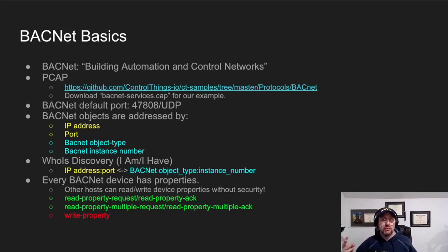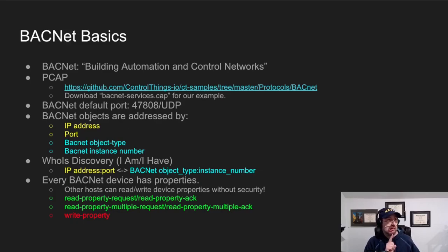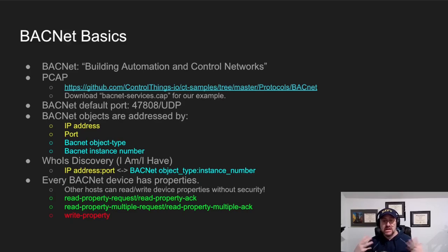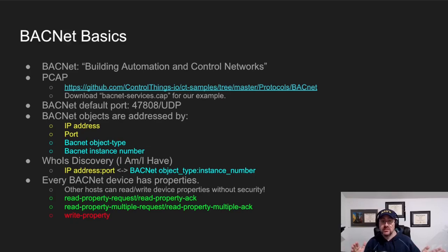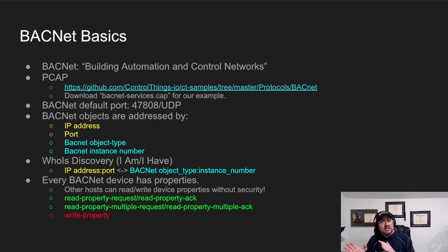Once you're on a BACnet network, there are two pieces of information you need to know to get to a BACnet object. One is the object type — it can be device, analog input, binary input, binary output, analog output, and so forth. These are different enums of the BACnet object type. The last piece of information is the instance number. So you can address an object by the object type and instance number — for example, device 104, or binary output 608.